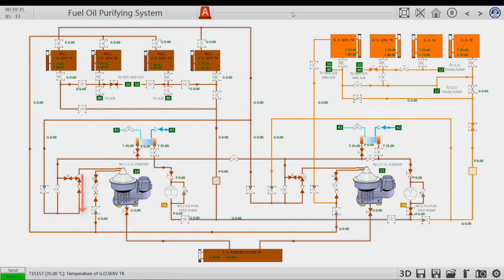This is the bypass line of the oil separator. When it needs to control the amount of separation, the bypass pipe is necessary. Fuel that is not passed through the bypass 3-way valve can return oil directly. If we need less separation, we can adjust by opening the throttle valve. This 3-way valve is used to control fuel inlet or bypass.